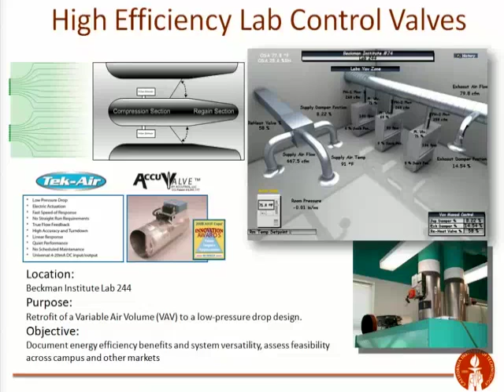This new valve that we're installing has fins, so it's independent of that pressure, so it can regulate the airflow to the fume hoods without any of that pressure. So that means that we can scale back the fan speed and change out to variable speed fans and significantly reduce the energy because we don't need that pressure to move the system around. So again, big savings. This is all being done in cooperation with the researchers in these labs, so it's absolutely critical that we're working with the users.